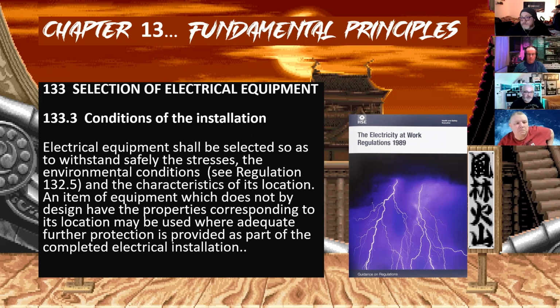Right, moving forward. Selection of electrical equipment, 1333, conditions of the installation. Electrical equipment shall be selected so as to withstand safely the stresses, the environmental conditions - see Regulation 132.5 - and the characteristics of its location. An item of equipment which does not by design have the properties corresponding to its location may be used where adequate further protection is provided as part of the complete electrical installation.